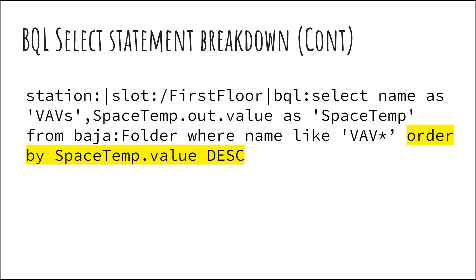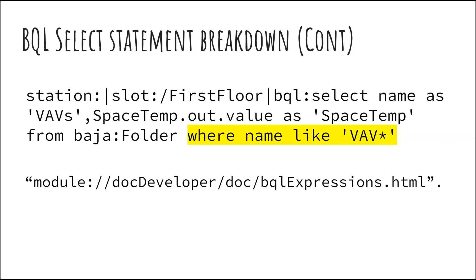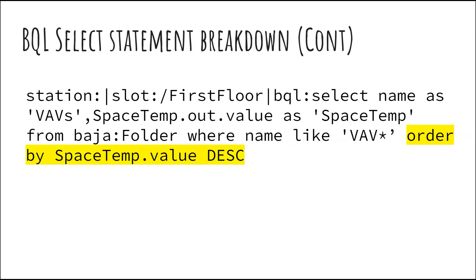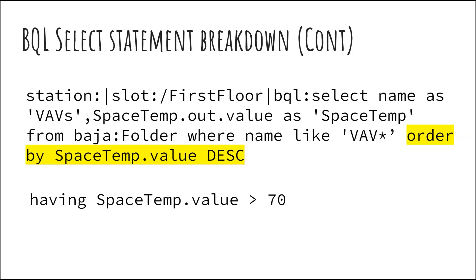Our final section is that we can reorder our results. This is where we can order our results, which can be very helpful in certain use cases. For example, we could sort rows by zone temp from highest to lowest using 'order by spacetemp.value desc.' Much like in our projection and predicate, we can use any specific property in a similar way to B format — going from lowest to highest with 'order by spacetemp.value asc,' alphabetize with 'order by name desc' or asc, or sort by slot path.